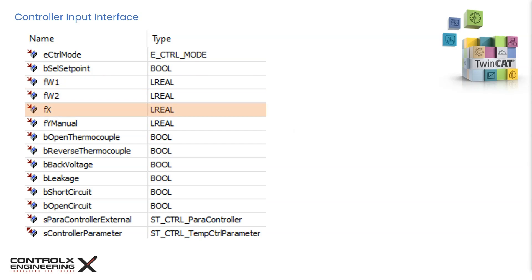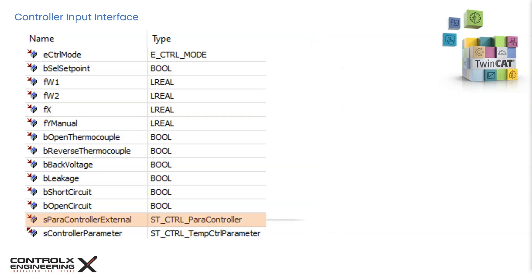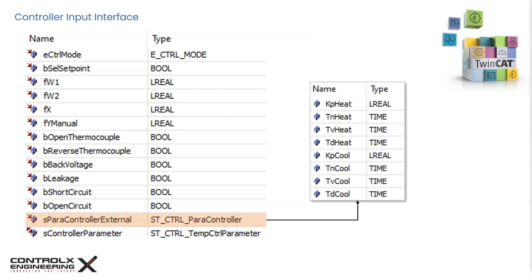FX is the actual or feedback value which is necessary for the closed loop controller action. It is of long real data type and expected units are degrees Celsius. The feedback, also known as the process value, can be brought into the PLC by means of thermocouples for example. We can make use of Beckhoff I/O terminal like EL3318 to get the process temperatures using thermocouples. Note that the data type for this terminal is usually of integer data type. So the scale temperature must be converted to long real before connecting to FX.